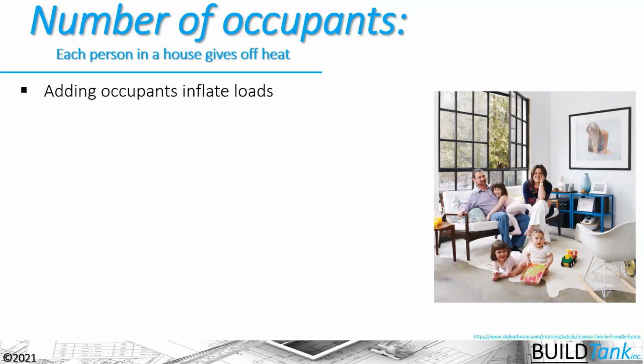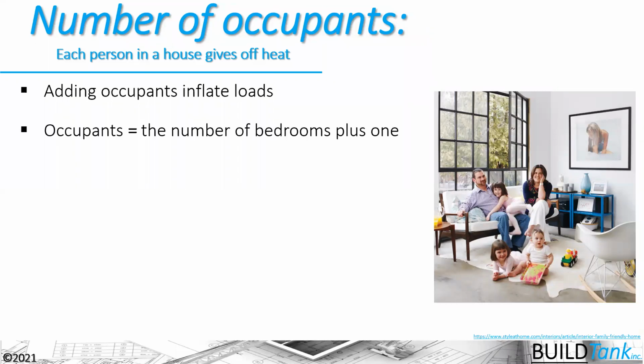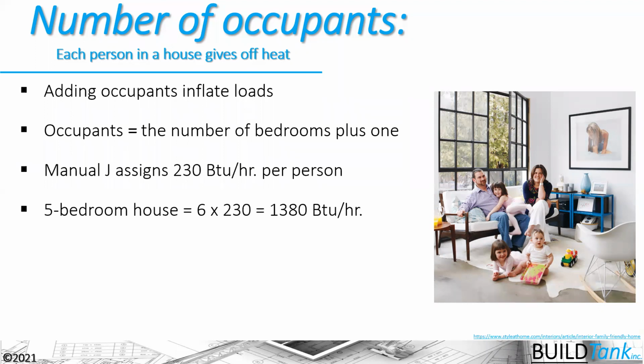The number of occupants is another thing that we should be looking at. Each occupant inflates the load or increases the load. The number of occupants is calculated by the number of bedrooms plus 1. It's the same way that we calculate the ventilation load for the house. Each occupant is about 230 BTU per hour that should be added to the house. So if I have a 5-bedroom house, it would turn into 6 occupants and 1,380 BTU per hour that would be added to the load of that particular house from a heating and cooling side equation.